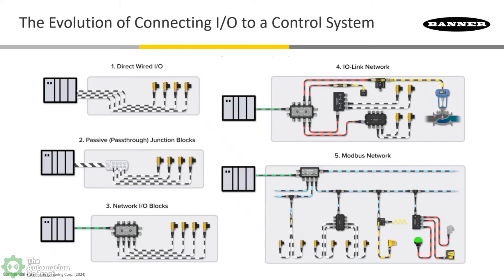When we say Remote I/O, we mean distributed I/O — those two words are used interchangeably. I know some people remember the old networks from the late '70s and early '80s, but we're talking modern-day distributed Remote I/O that you wire your devices into and then goes back to your control system. A lot of the major PLC vendors are telling me that in many instances, people are just buying the PLC, putting it in its own little rack, and using 100% distributed Remote I/O. Local chassis I/O is often more expensive than distributed or remote I/O.